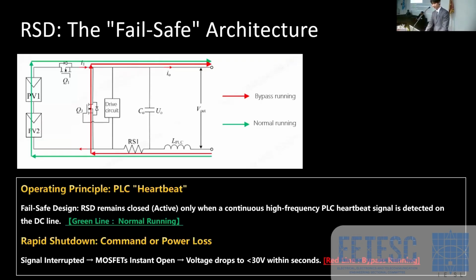For this slide, I want to show you how rapid shutdown actually works. We use a technology called PLC. As you can see from this diagram, the green line is normal running. Basically, Q1 is always closed and Q3 is open. Okay, let me go back to the PLC. The PLC is power line communication. You can think of it as a heartbeat signal. People die when the heartbeat stops, right? So the point is how to control the control signals.